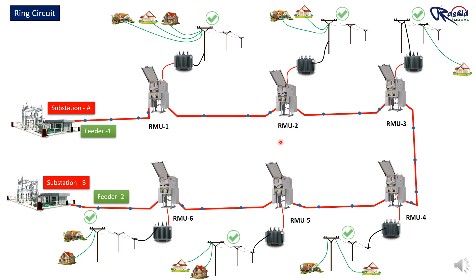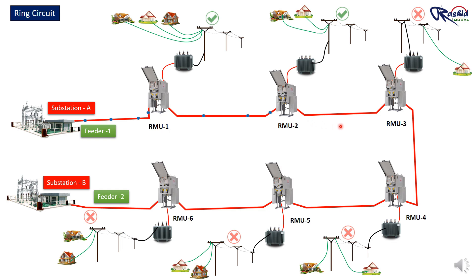When a fault is detected between RMU2 and RMU3, the switches in RMU2 and RMU3 are used to isolate the fault. The switch on each side of the faulty section is opened, effectively removing the damaged part from the circuit. When the faulted section is isolated, Feeder 2, which is connected to substation B, can now be used to supply power, and power can flow from Feeder 2 to all RMUs and transformers on the network, maintaining a continuous supply to the load.